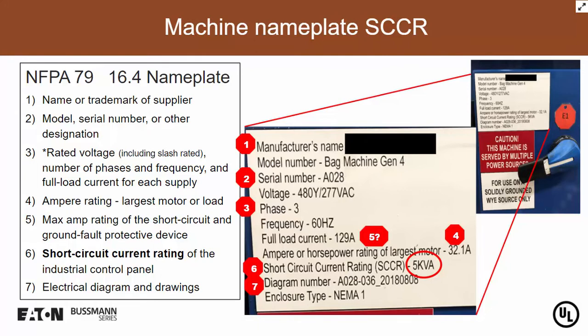And while we're looking at this nameplate, I'd also like to point out that item number 5 in the list from 16.4, the nameplate does not satisfy that requirement. It's not showing the maximum ampere rating of the short circuit and ground fault protective device to be used to protect the machinery. So this is a typical nameplate, and this is where you would express the short circuit current rating. It would be provided with the other electrical parameters required in paragraph 16.4 of NFPA 79. And that would also, of course, match with Article 670 requirements for industrial machinery.